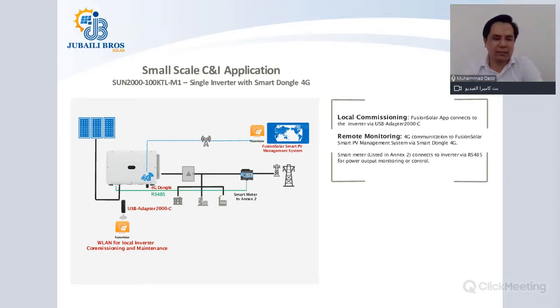So again, if we have a small scale C&I application and we are using a 100 kTL inverter, which is the largest low voltage inverter from Huawei. In this scenario, for local commissioning, since it comes with the USB adapter free of cost, you can use that and do the local commissioning using the FusionSolar app. And for remote monitoring, in this scenario, it is shown that you can use 4G dongle, and so you have the only option of 4G communication with the FusionSolar cloud.